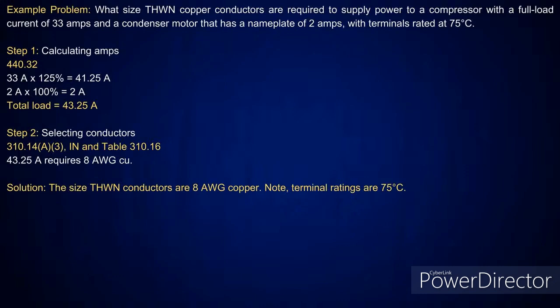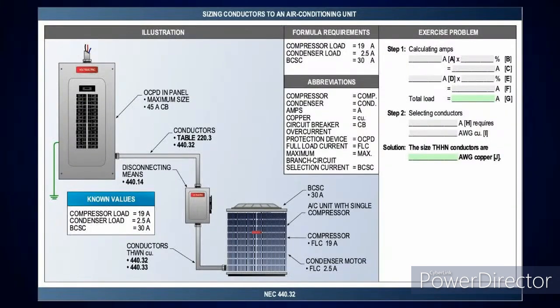Now, as I look at this AC unit, same thing. I've got a 19 amp compressor and a 2.5 amp condenser. How do I do it? 19 amps is at 125%. The condenser is at 100%. Add all those amperages up, then size conductors based on table 310.16 and the 75° C column.